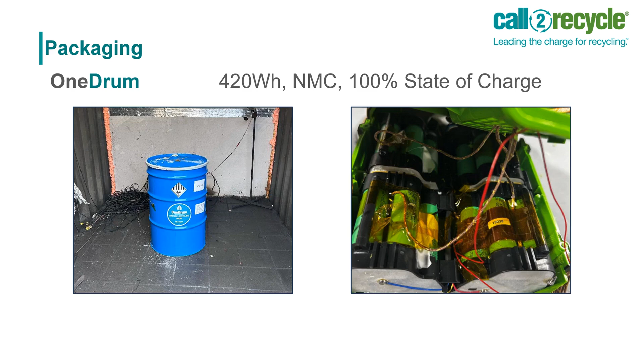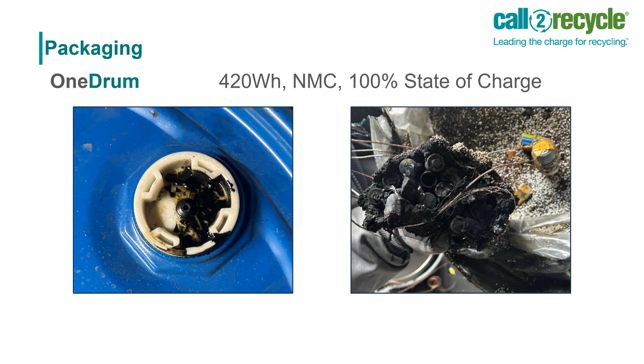This is that one drum I mentioned, we throw the batteries in, 420Wh, NMC, 100% state of charge, with a 2 PSI vent plug so you don't get a dangerous buildup and accumulation of gas. You can see that battery was fully consumed in that test.